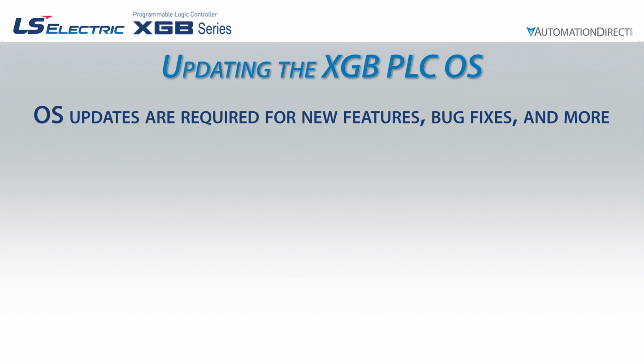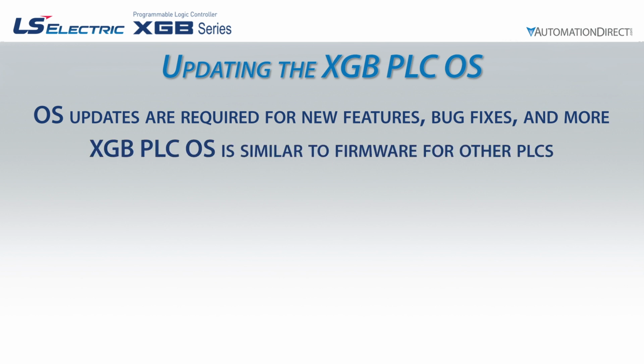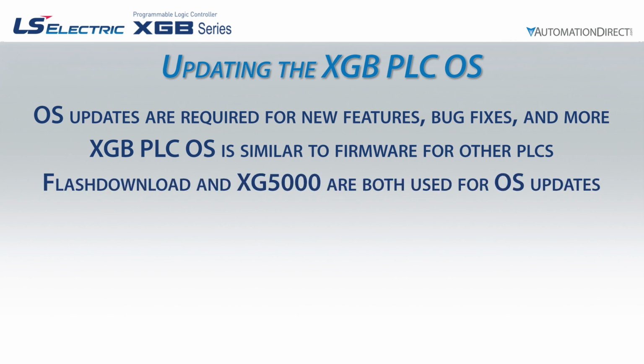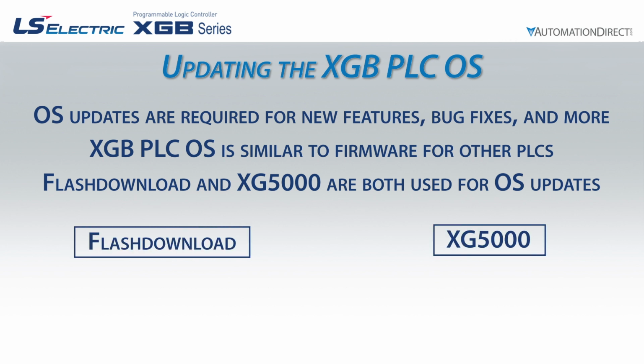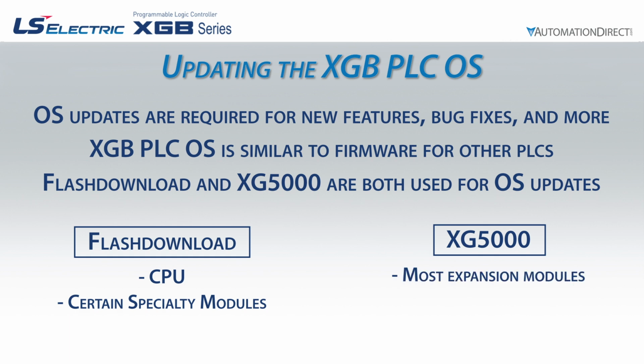For the XGB PLC, the OS is similar to firmware in other PLCs. OS updates for the XGB PLC will either use the flash download utility or the XG5000 software. The CPU and a few other modules will use flash download, whereas most expansion modules will use the XG5000 software. The flash download software, as well as current OS files, may be found at AutomationDirect.com.